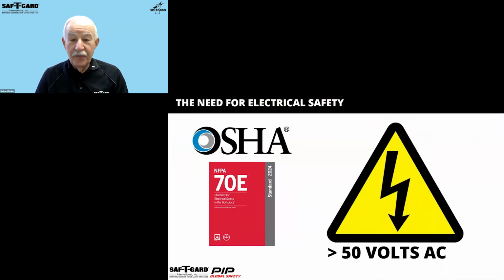OSHA rules and NFPA 70E, which governs workplace electrical hazards, require the use of rubber insulating products when even the smallest probability of contact with 50 volts AC or higher exists. Let's repeat that. OSHA rules and the NFPA 70E standards, which is also referenced in OSHA, require the use of rubber insulating products when even the smallest probability of contact with 50 volts AC or higher exists.